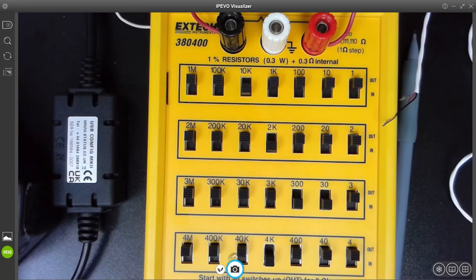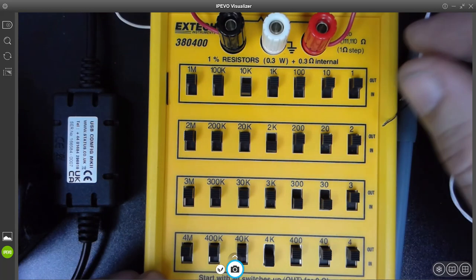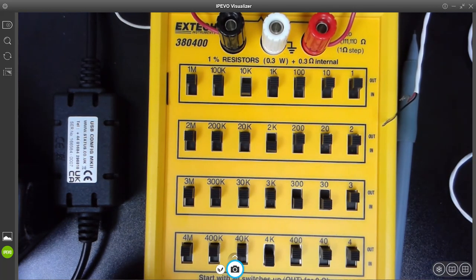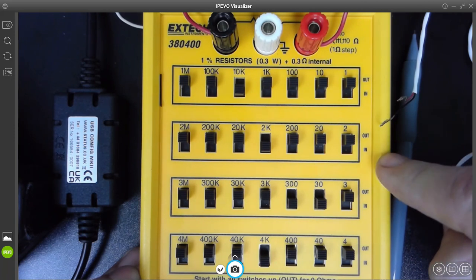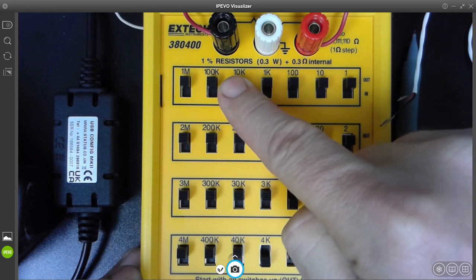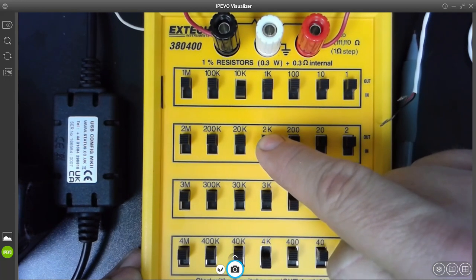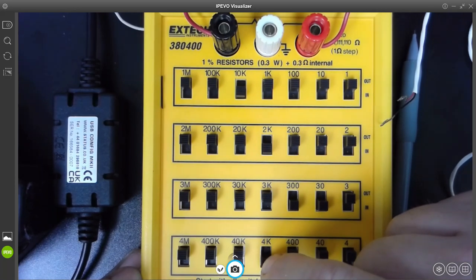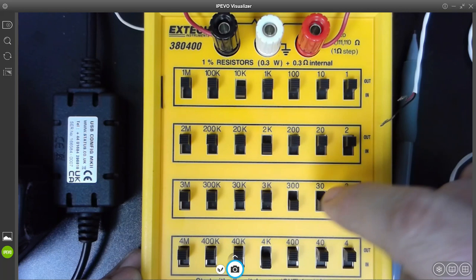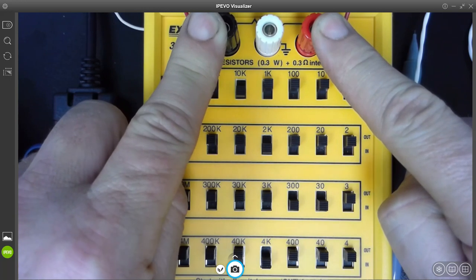At this point, I have disconnected the thermistor and hooked up our decade resistor box. We are going to send our low signal, which for this calibration range is 16,330 ohms. To set the decade box, everything that is pushed up is not in the circuit. So when I pull something down, it puts it in. So I'm doing 16,330 ohms. I'll pull down the 10K, the 2K, and the 4K. That adds up to 16,000. I need 330, so I'll pull down the 300 and the 30, and this will add 16,330 ohms of resistance between these 2 points. And that should simulate our low end of the scale, which is 32 degrees Fahrenheit.